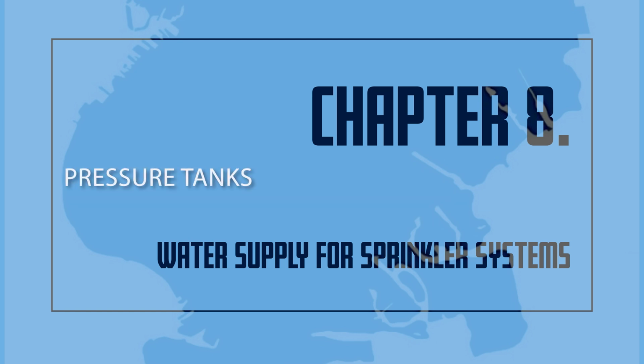Pressure tanks. Pressure tanks have several possible uses in automatic sprinkler fire protection systems. The tank is normally kept at two-thirds full of water and one-third full of air. The air pressure in the tank shall be maintained at or above 75 psi. Air for pressure tanks is supplied by air compressors. Because the water is always under pressure, it can be forcefully distributed throughout the sprinkler system. An important limitation is the small amount of water that can be stored in such tanks. Where a small pressure tank is accepted as the water supply, the system is called a limited supply system.